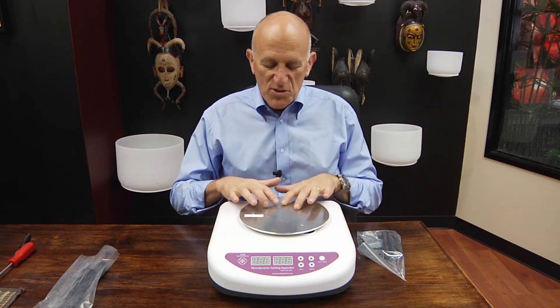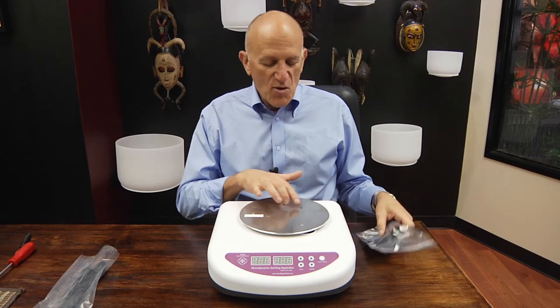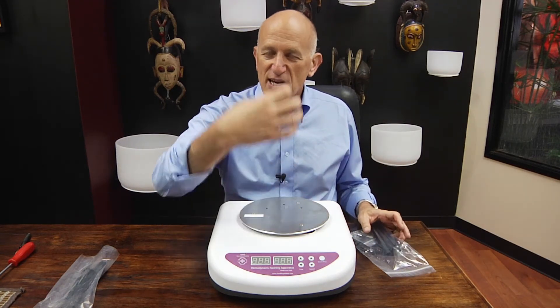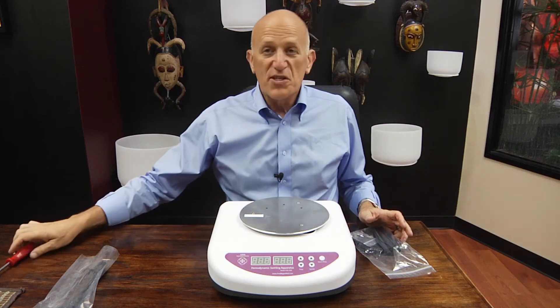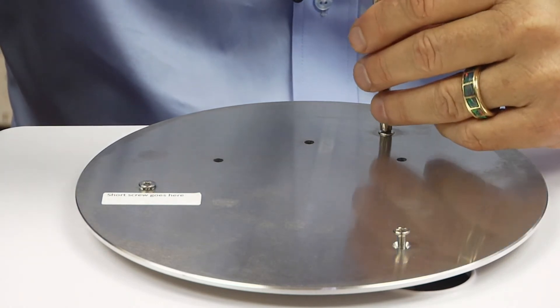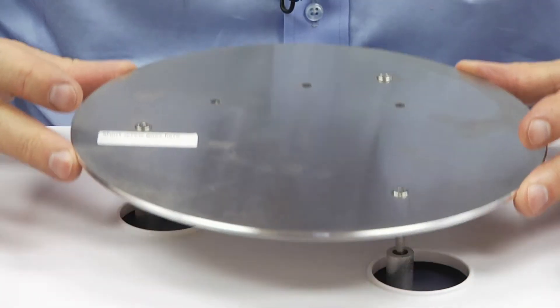These three holes here are the back of the machine where the cradle sits. The front of the cradle is open because the IV set sits in it. The first thing you would do with a regular Phillips screwdriver is unscrew the platform so that you can get access to the bottom.